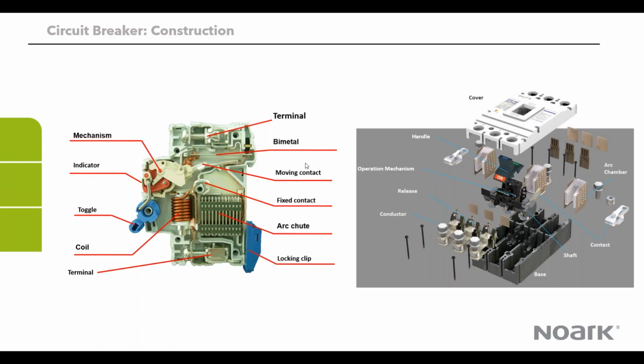But because it's a bimetal and it takes time to actually build up the temperature, so it takes a longer while. Then we have the contact. This is an important part of it, where you have the moving and the fixed contact. So that's where you have the connection between the load side and the line side of the circuit. So that's where you have the actual connection, the contact that is made, maintained, or interrupted.